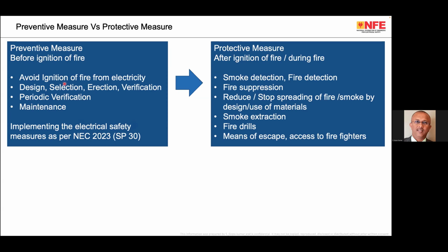One simple example: imagine you have a lighting circuit where the total load of the lights is only maybe 2 amperes, 3 amperes. But if you put an MCB of 16 amperes and a 1.5 square mm wire, of course you will be in trouble. Maybe people say, I am using this 16 amp MCB and 1.5 square mm wire for the last 25 years, no fire occurred. This is not the correct statement.